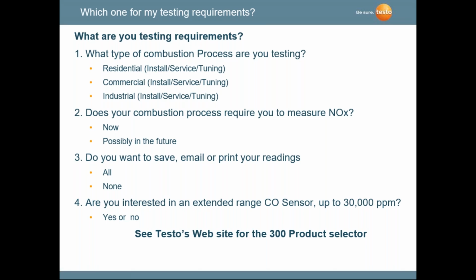Do you want to save, email, and print your readings? All the 300s save, email, and print readings. Now, with the printing side, you need the printer, of course, but it has the capability. All 300s have the capability of printing to a Testo Bluetooth printer. And then are you interested in extending the CO sensor range? We have a model that I'll go through that goes up to 30,000 ppm on the CO. In case you want to look at carbon monoxide and you want to look at oxygen and you're adjusting your air ratio, and you're trying to minimize the oxygen down to a point where you start building up high concentrations of carbon monoxide, we have an analyzer that's capable of doing that.